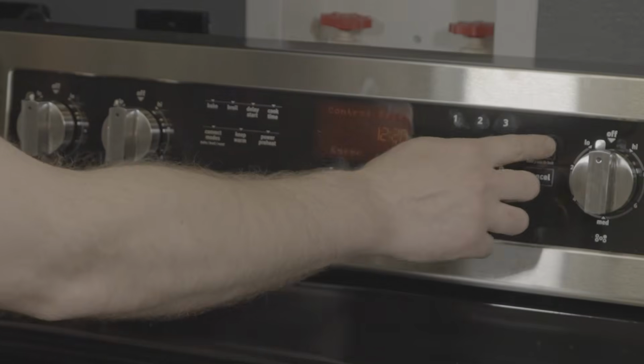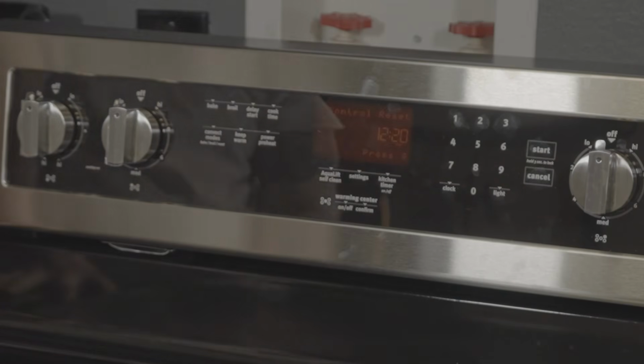Now, once you went through the fault codes in the system and fixed whatever you wanted to fix inside of it, the next thing you want to do is a control reset. To do a control reset, let's go ahead and exit out of the faults. Go ahead and press cancel start one more time and scroll with the number 3 all the way to, I think it's the 6th number, and it will say control reset. Go ahead and press start, reset the whole unit, and start from scratch.